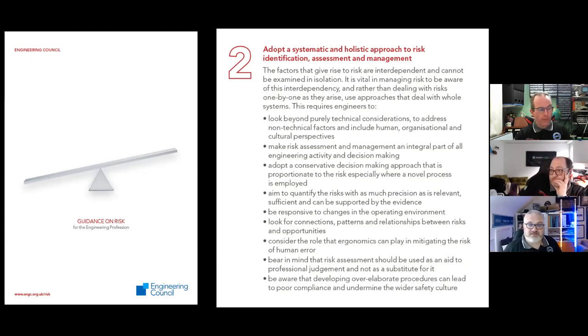Aim to quantify the risks with as much precision as is relevant, sufficient, and can be supported by evidence. When I get an EICR document given to me, I want evidence, otherwise I throw it in the bin. I want justification. This is why I generally say good practices. If you're issuing a report now, use something like SitePro and get it all photographed so you can code it as well and give it to the report. I wish to God, to be honest with you, half these reporting softwares did that now. The key thing there is timestamping your photos, timestamping your evidence. Timestamping is key, especially if you have to go back and your work is warranted in a domestic world.